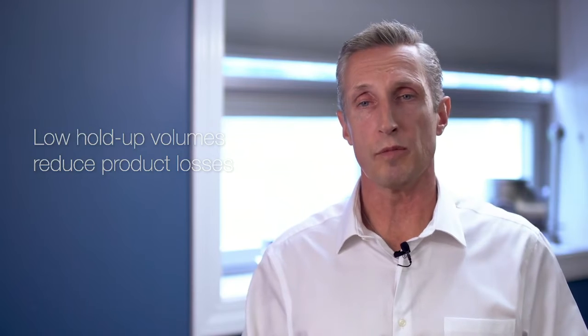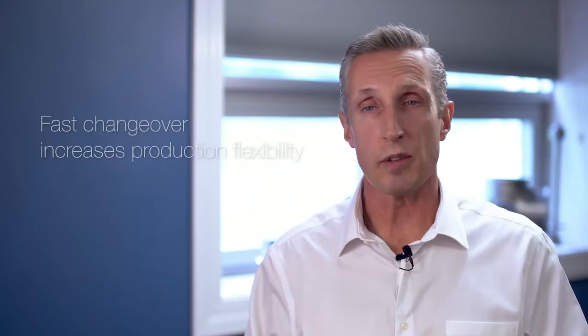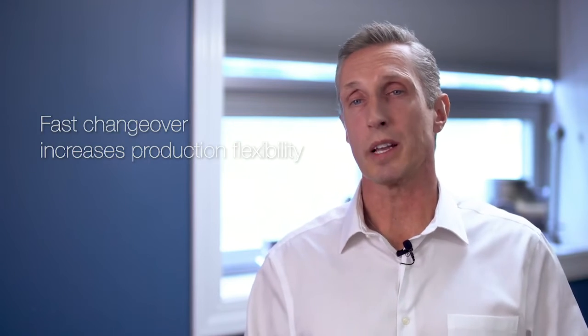As far as the differences between static heat exchangers and scrape surface in terms of product changeover, I would say that scrape surface heat exchangers are extremely versatile, and they have a relatively low product holdup volume. So when a customer needs to either finish a process and enter cleaning or transition from one product to the next, this is where the scrape has an advantage, because as the product is transitioning, there's very little holdup volume in there, there's very little intermixing, so they can really maximize their product gains.